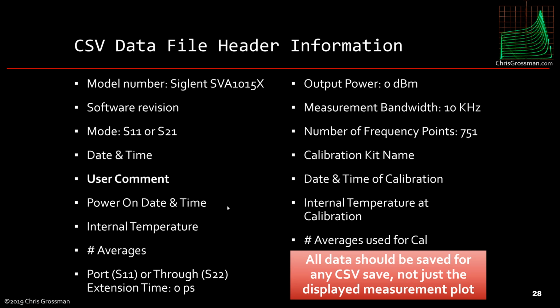because I want to know how long it's been since I powered this unit on, because calibration, things drift with time, and I want to know if I made this measurement 3 minutes after I turned it on or after it's been sitting there half a day and stabilized. I'm sure they have some sort of internal temperature they can measure in the unit. And it's good to know this because I want to be able to compare this internal temperature from measurement to measurement and with the calibration, just so that if there's something screwy with measurements later, this is one of the things I could check. I want to know how many averages I've used for that measurement.